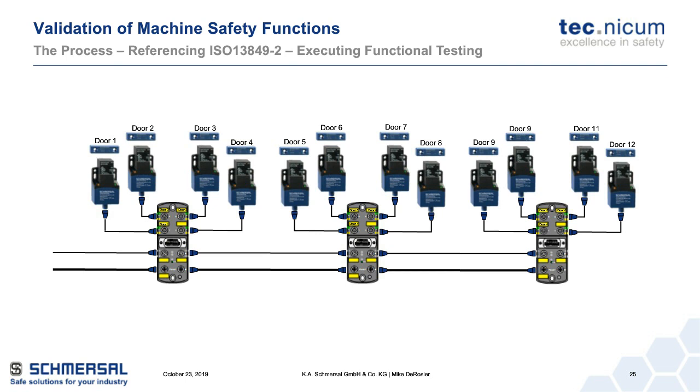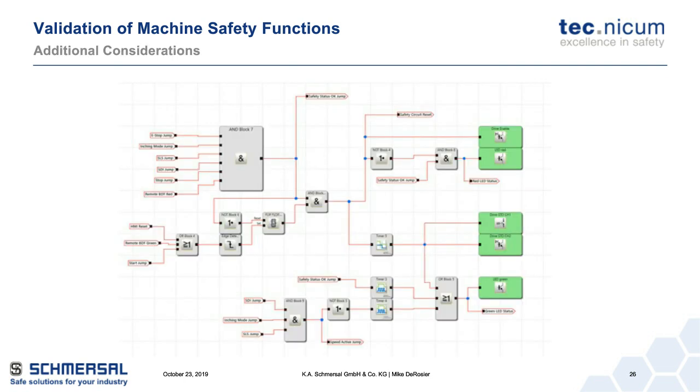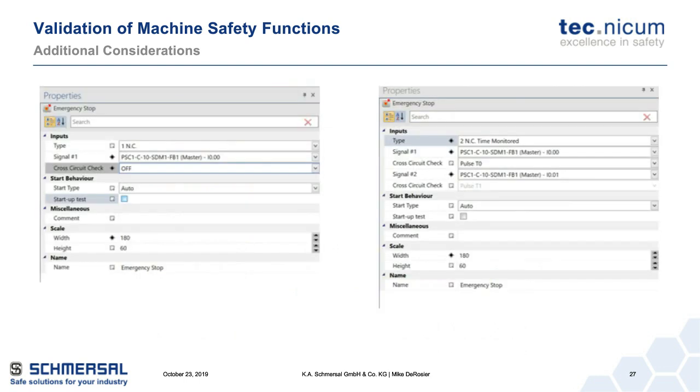When we look at software and function blocks, here's a page of code that shows some logic of certain safety devices when they're triggered to allow safe torque off to engage and do different things with AND gates and OR gates. So that's all great. But based off of that, can you follow that flow and say that this is all okay? They're safety function blocks, or they're safety inputs, or single inputs to them. But what does that really come down to at the end of it?